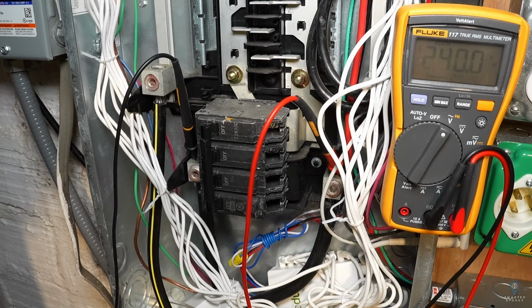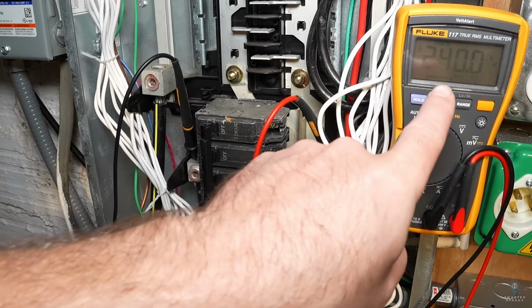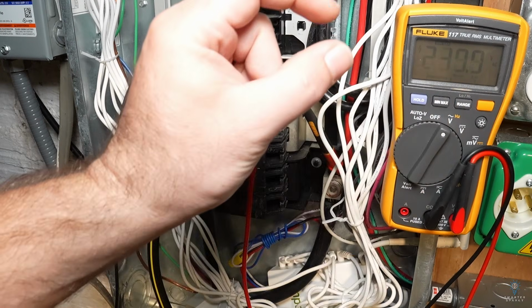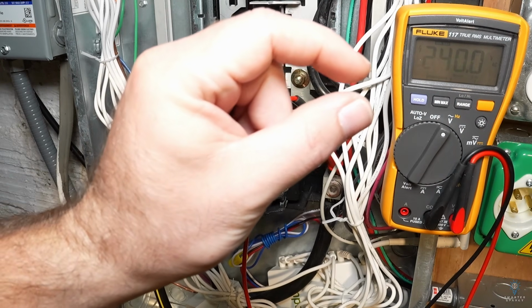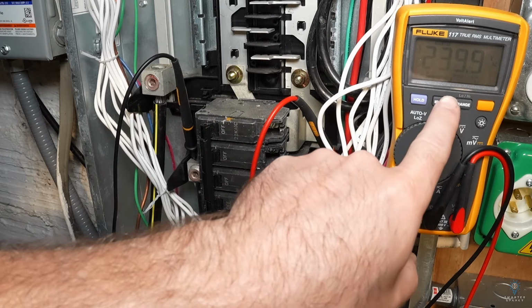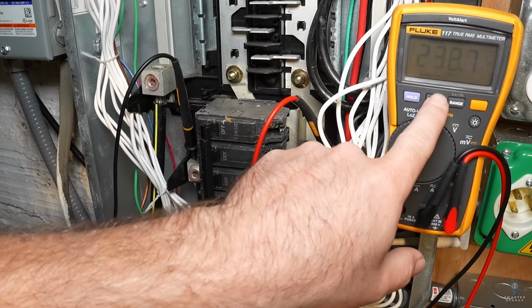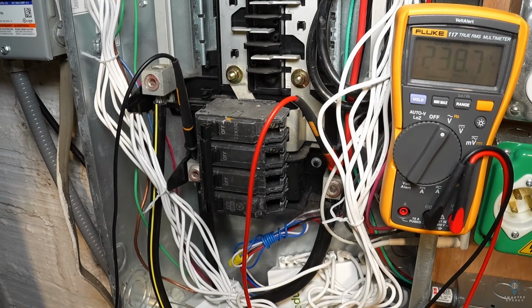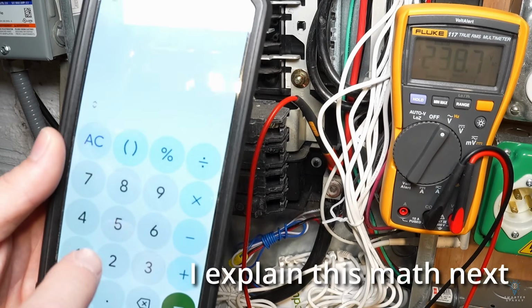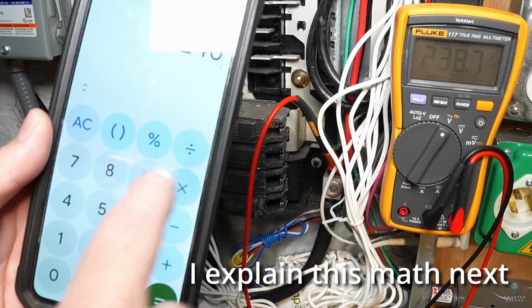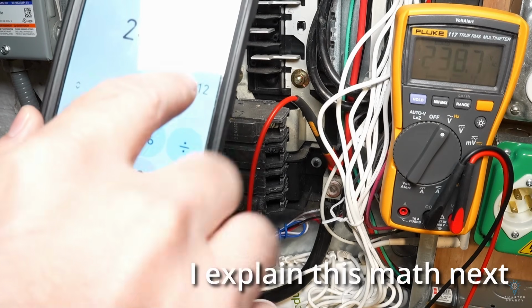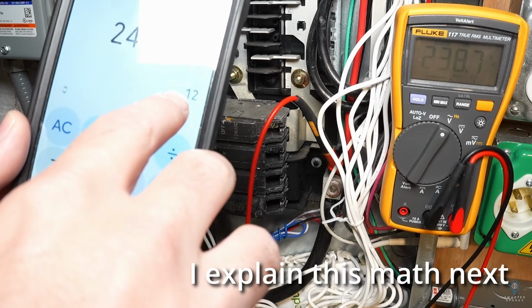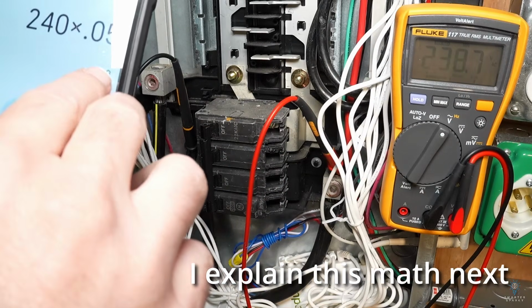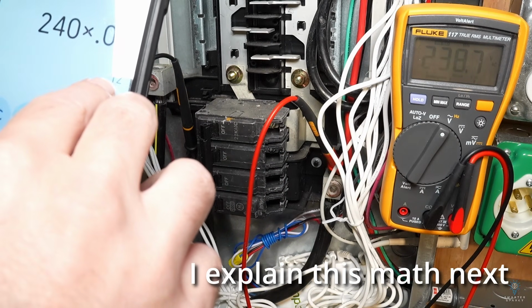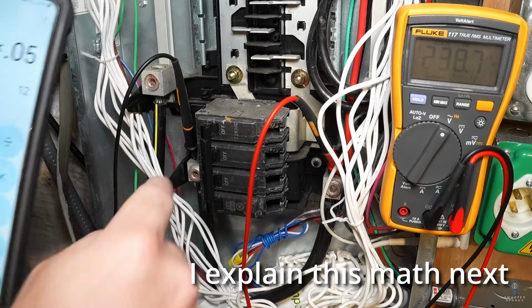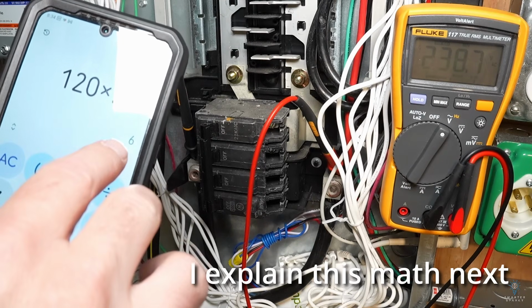All right, there the dehumidifier just kicked back on, and we saw that the voltage fluctuated a tiny bit, but not a whole lot. And if we go back to min max, our max is 242 and our min is 238, which if we take a look at the math on that, we got 240 volts times 5%. So from line to line, we're allowed to deviate 12 volts. But from line to neutral, we're only allowed to deviate 6 volts.